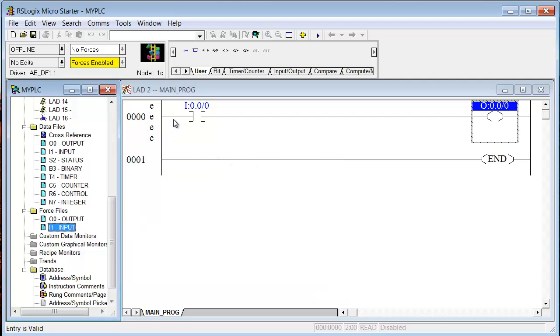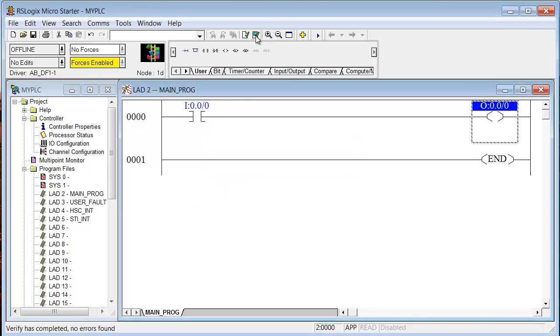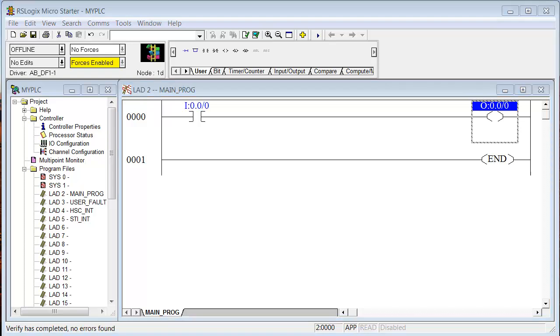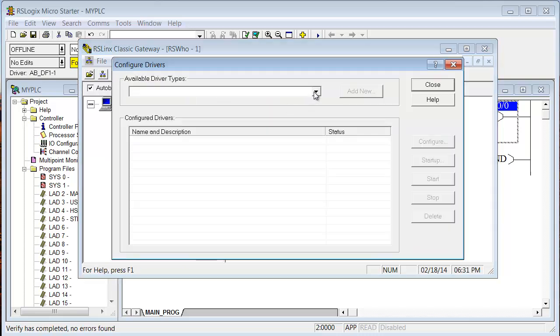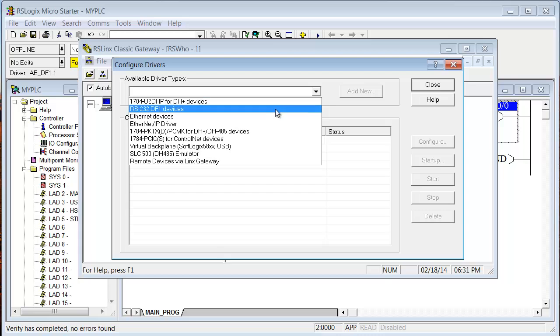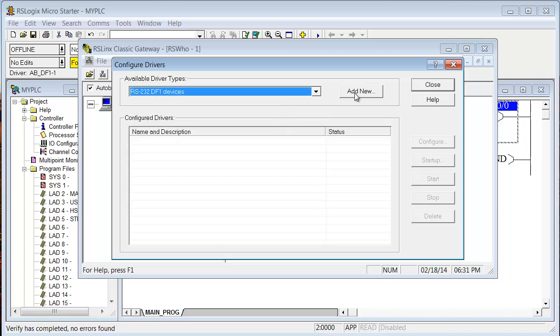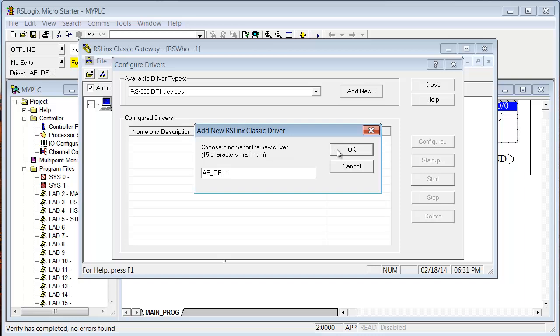Now, this rung is still in the edit mode, as you see by the E's. I would normally just verify the project if it likes it. The E's disappear, and there's no errors that pop up. Now, we want to download this. So the first thing that we have to do is set up RSLinx. So we open up RSLinx. It opened up out of your view, so I will drag it over. There's RSLinx, and we go to the double-headed snake, configure drivers, and we pick the RS232 DF1 devices. This is the simplest driver. Any MicroLogix or SLC 500, as a matter of fact, any Allen-Bradley PLC that has an RS232 port on it, supports this driver. And this is a point-to-point, no addresses to fool around with. And it supports AutoConfig. I'll show you what I mean. So you pick that, say Add New, leave the default name.